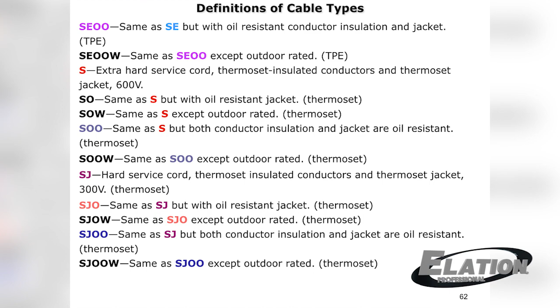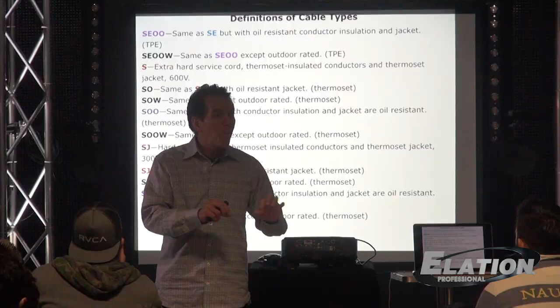Then type SJ is only hard service cord. It's not extra hard, it's hard service cord. What that means is, if it's type SJ, and you see it all the time if you start looking at the cable markings, sometimes out in the field you'll see type SJ cable. What that means is you're not supposed to run it along the floor, because if somebody steps on it, or if somebody runs a forklift over it, it could cause a break in insulation, and now you've got a problem.